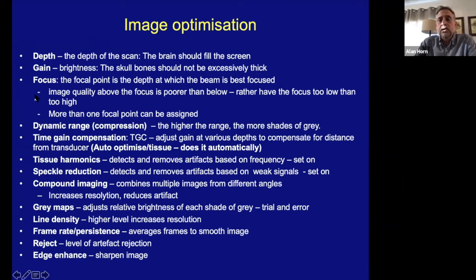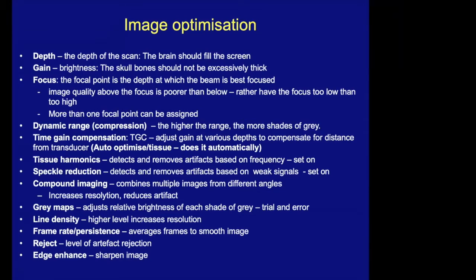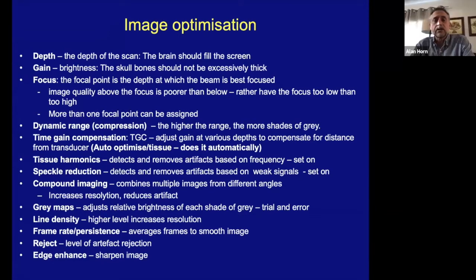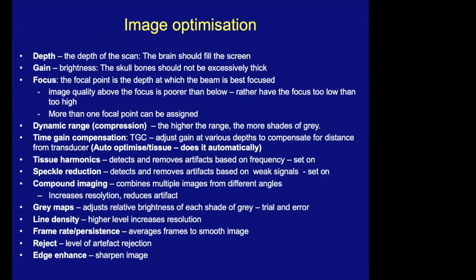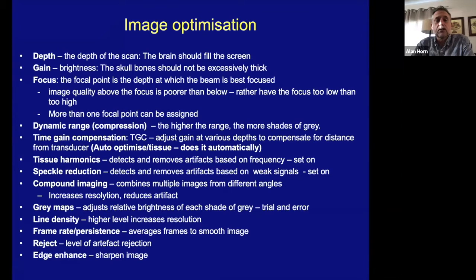The focal point is the depth at which the image is focused, funnily enough. And that should not be set too high. If it is, then the image will deteriorate below it. So rather set the focal point far down rather than too high up, or add additional focal points. The dynamic range or compression determines how many shades of gray you have. The time gain compensation adjusts the image at various depths, and this can be done automatically on most machines.